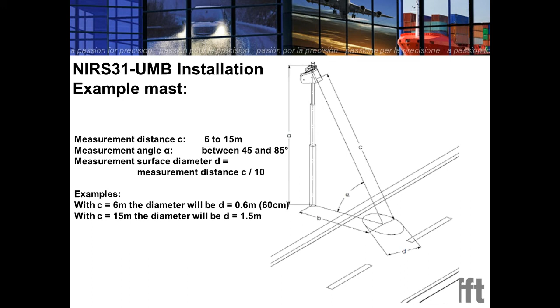Not rain, not precipitation. That has nothing to do with precipitation here. The NIRS is not able to measure precipitation. That's not a precipitation sensor or a snow height sensor. The sensor NIRS is able to check the layer on the surface, to check the height up to 10 millimeters for snow, up to 2 millimeters for water. That's it. Not a precipitation measurement here. Don't mix that up. Right, so let's go on. Thank you for the questions.